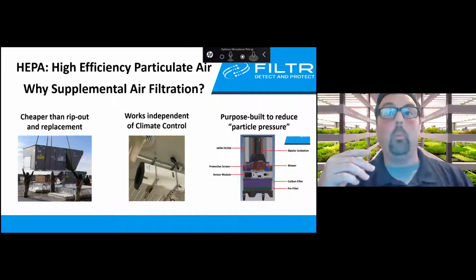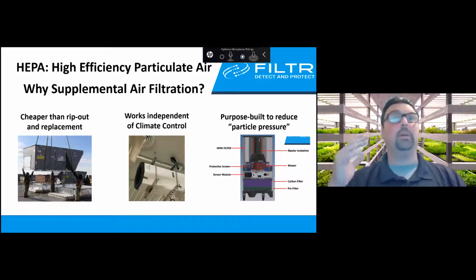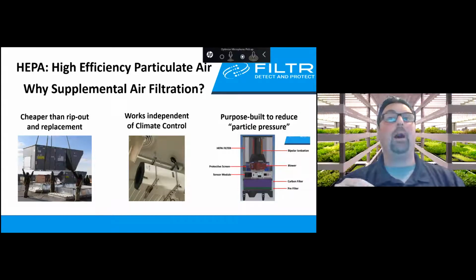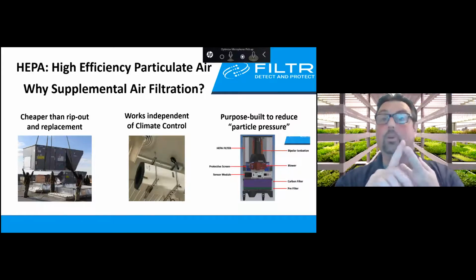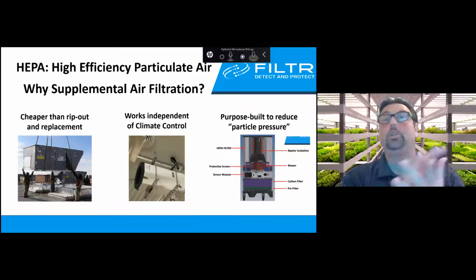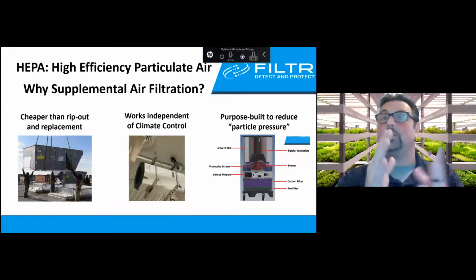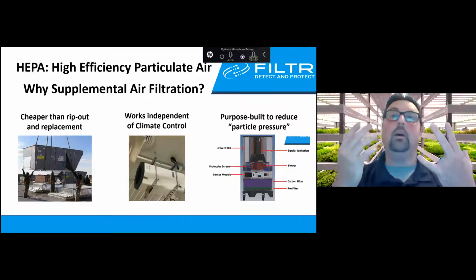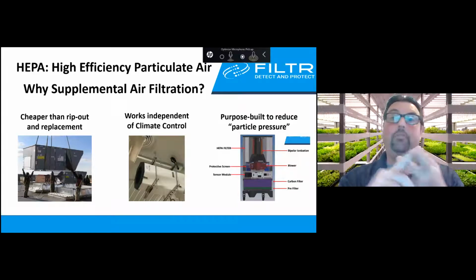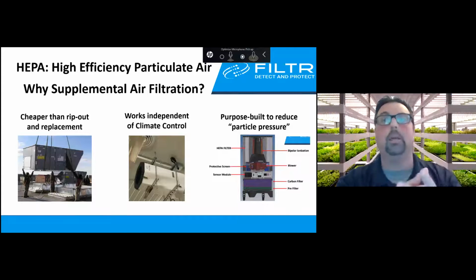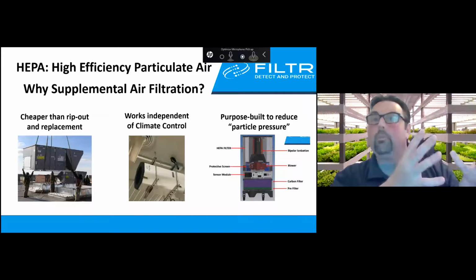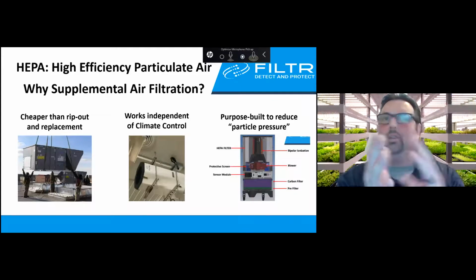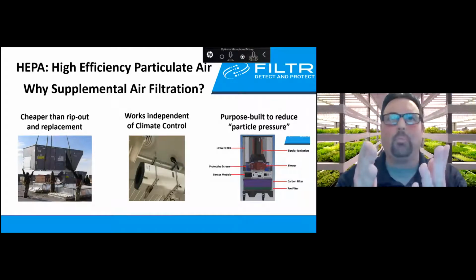That's so much easier to do because it's cheaper than ripping out and replacing an entire HVAC system that already satisfies the cooling needs of the room, just to get better filtration. That doesn't make sense to me. If you weren't cooling the room enough and had mold problems, I'd say you need a rip out and replacement. But if one part of the problem is being solved and the other isn't, you can just bring in something to solve that other problem.